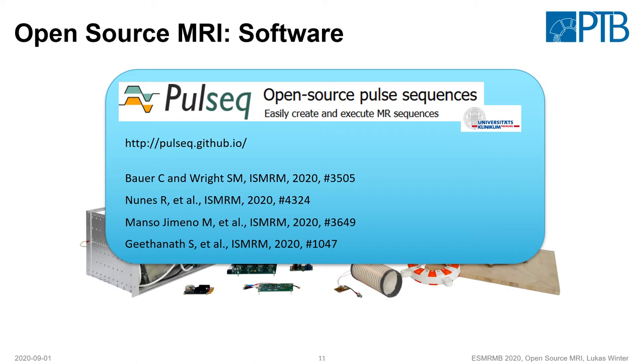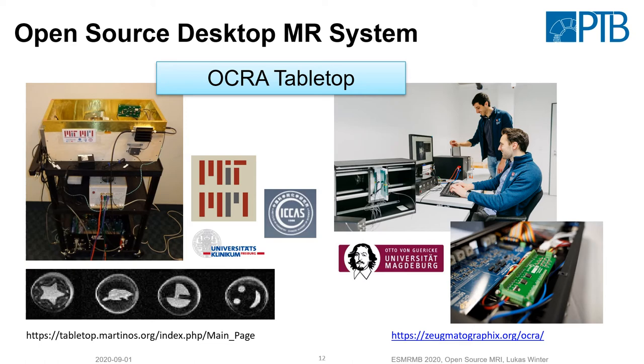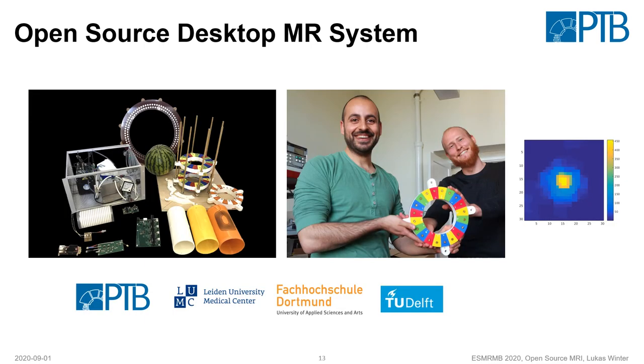Here are some recent ISMRM abstracts that use this tool. When we put these pieces together we already have some complete systems. Starting with the first, it's the OCRA tabletop — an open source desktop MR system that fits on the desk. It has a relatively small field of view but for educational purposes it's great, giving very good imaging performance. It was originally designed by MIT MGH, and Magdeburg also successfully rebuilt it and extended its functionality.